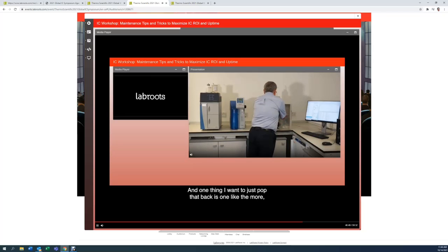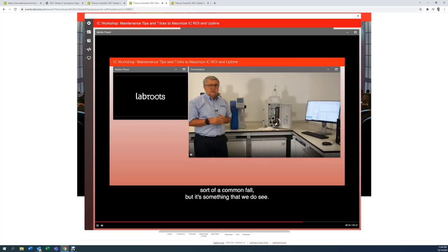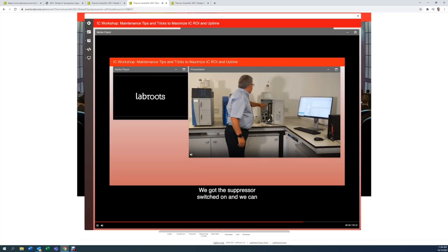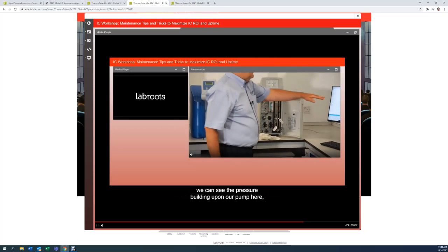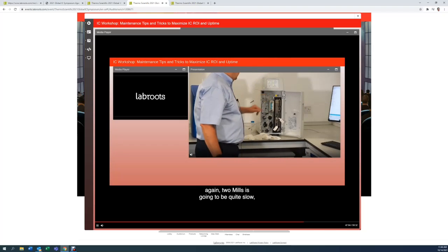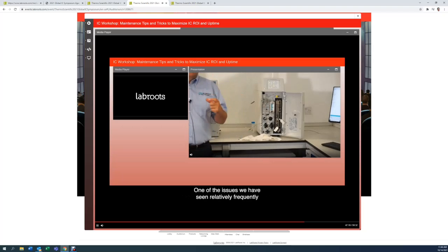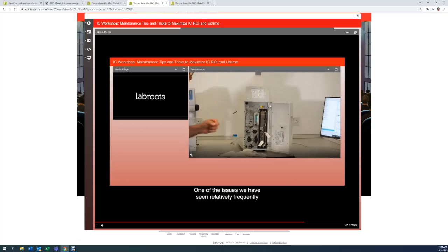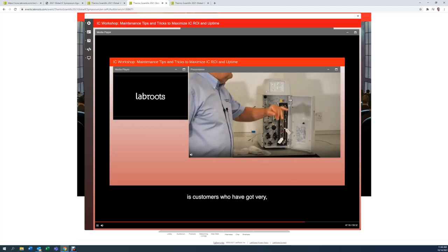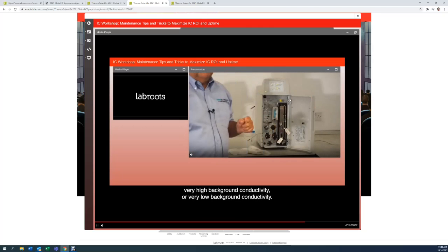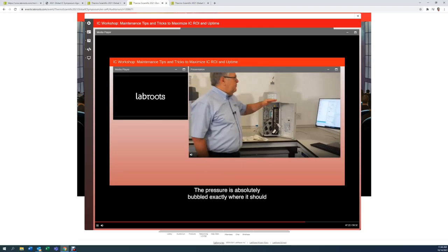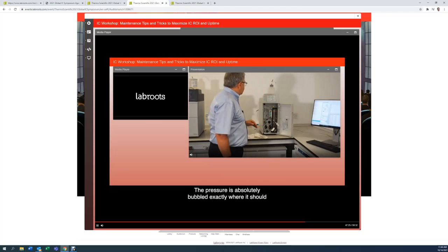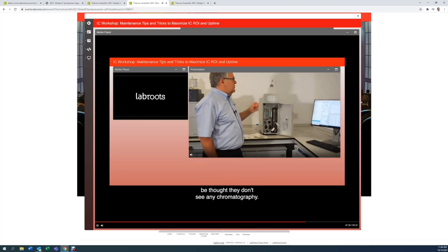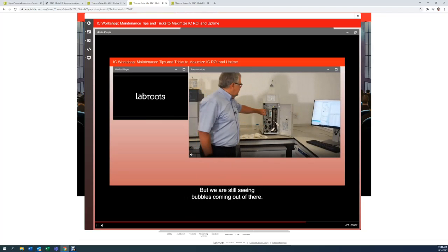And one thing I want to just pop that back is one of the more, it's not sort of a common fault, but it's something that we do see. We've got the suppressor switched on, and we can see bubbles coming out of the suppressor, and we can see the pressure building up on our pump here. Again, 2 mils, it's going to be quite slow, but we can see bubbles coming out. One of the issues that we have seen relatively frequently is customers who have got very, very high background conductivity or very, very low background conductivity. The pressure is absolutely bang on, exactly where it should be, but they don't see any chromatography. But we are still seeing bubbles coming out of there.